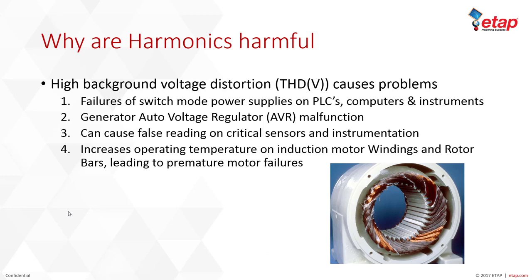High background voltage distortion, or total harmonic distortion voltage, also causes problems. It can cause failures of switch mode power supplies, PLCs, computers, and instruments. If you have PLCs or power supplies that are burning up, it may be a good idea to perform a harmonics study. Generator automatic voltage regulators can malfunction with serious voltage distortions. It can also cause false readings on critical sensors and instrumentation, and increase operating temperature on induction motor windings and rotor bars, leading to premature motor failures.